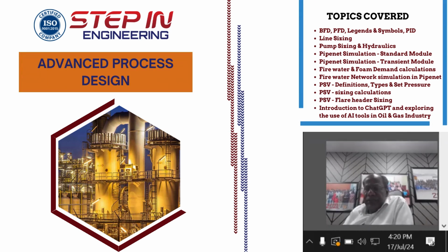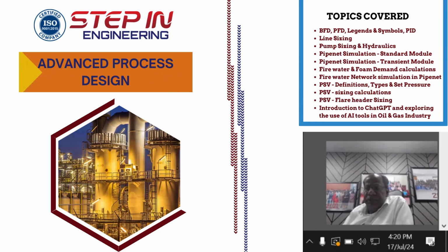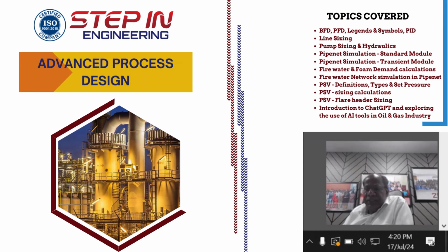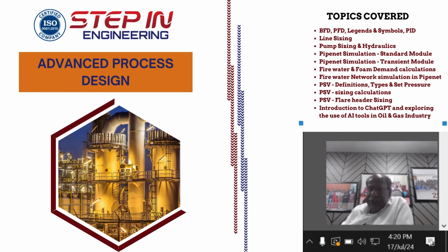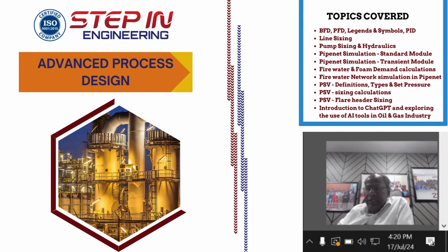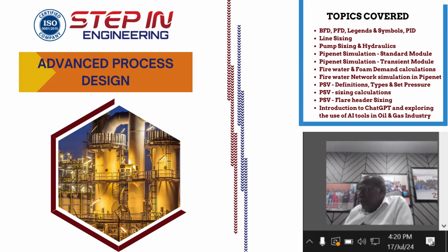So delta P per 100, if it is a gravity line, the velocity should not be more than 1 meter per second. That is not my design. It is something which is stated in the good engineering practice like Shell DEP, etc., and I am going to give the reference, not only just say it, but show where it is stated. So there are so many things in the line sizing which I have already given in the course contents.